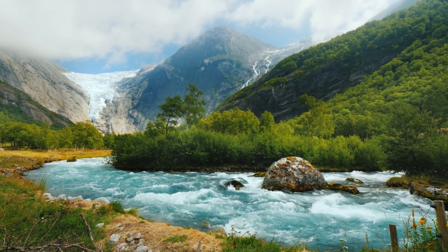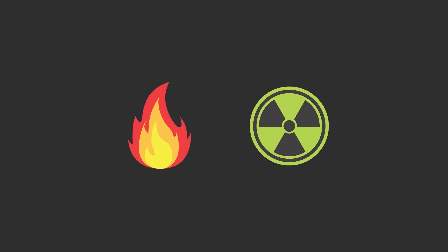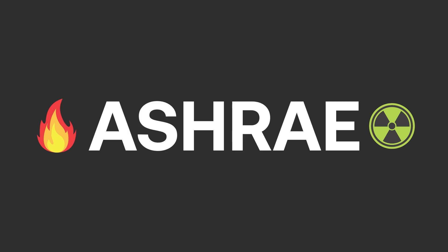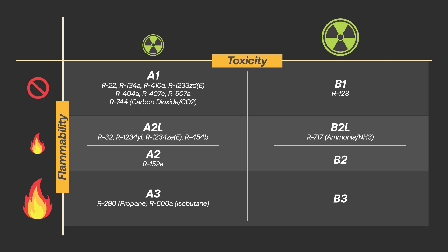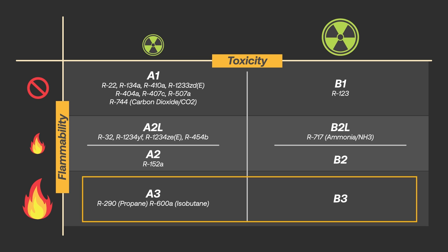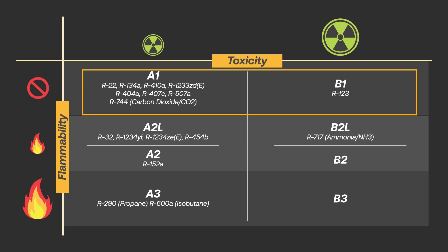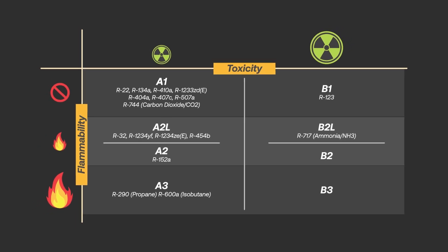These environmental impacts of ozone depletion and greenhouse gas effects caused by uncaptured refrigerants are the main driving factors for why we recover refrigerants in the first place. Another reason for recovery is the unnecessary cost of replacing reusable refrigerant that has been removed for system repair. These cost savings are compounded as the continued phase-down of HFCs occurs. Along with environmental dangers, refrigerants are also harmful to living beings. There are different levels of flammability and toxicity that can cause asphyxiation and/or physical harm. ASHRAE — the American Society of Heating, Refrigerating and Air-Conditioning Engineers — classifies refrigerants by hazard based on toxicity and flammability through Standard 34. Toxicity is signified with the letter A or B, while flammability is rated numerically: 1, 2L, 2, or 3. Class III refrigerants are highly flammable, class II are less flammable, class IIL are mildly flammable, and class I refrigerants show no flame propagation. Understanding these differences will help you choose the best equipment for each specific system and job.